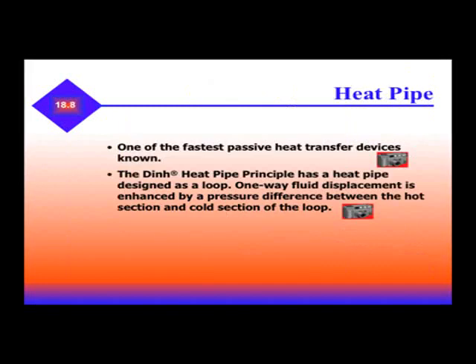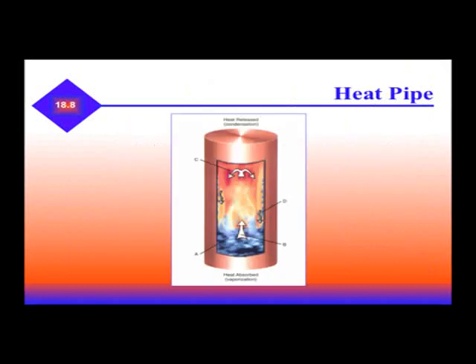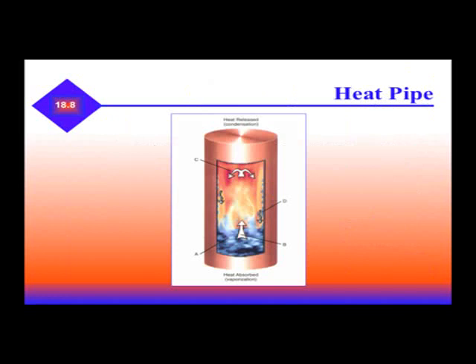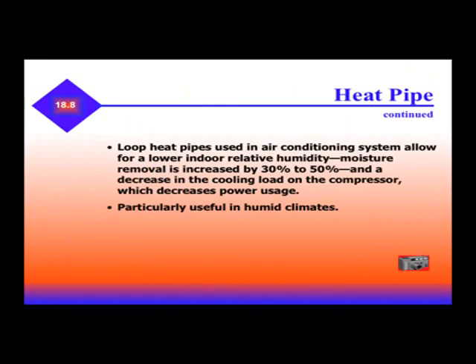The heat pipe is one of the fastest passive heat transfer devices known. The Dinh® heat pipe principle has a heat pipe designed as a loop. One-way fluid displacement is enhanced by the pressure difference between the hot section and the cold section of the loop. Heat is absorbed and heat is released through condensation. The higher the temperature, the more moisture is removed. Loop heat pipes are used in air conditioning systems, allowing for lower indoor relative humidities, with moisture removal increased by 30 to 50% and a decrease in the cooling load on the compressor, which decreases power usage.